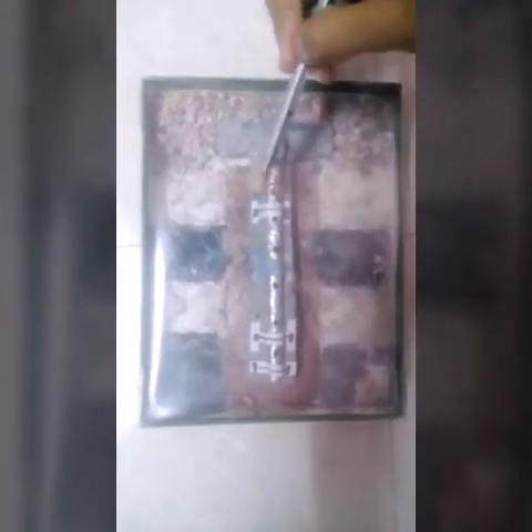Here we can see the pipe which we are using. Alternate layers of coke and salt are provided here to decrease the resistance of the earth. The depth at which the pipe must be buried depends upon the moisture content of the ground.